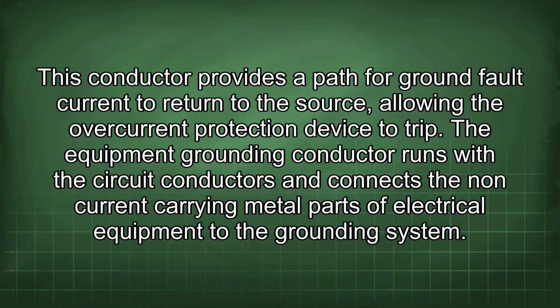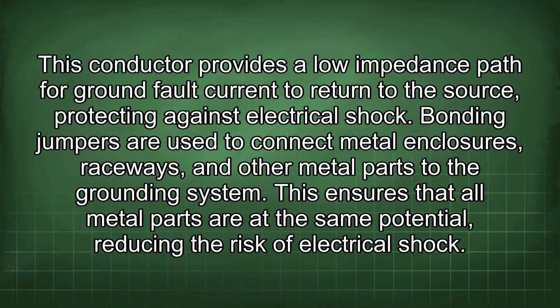This conductor provides a path for ground fault current to return to the source, allowing the overcurrent protection device to trip. The equipment grounding conductor runs with the circuit conductors and connects the non-current carrying metal parts of electrical equipment to the grounding system. This conductor provides a low impedance path for ground fault current to return to the source, protecting against electrical shock. Bonding jumpers are used to connect metal enclosures, raceways, and other metal parts to the grounding system. This ensures that all metal parts are at the same potential, reducing the risk of electrical shock.